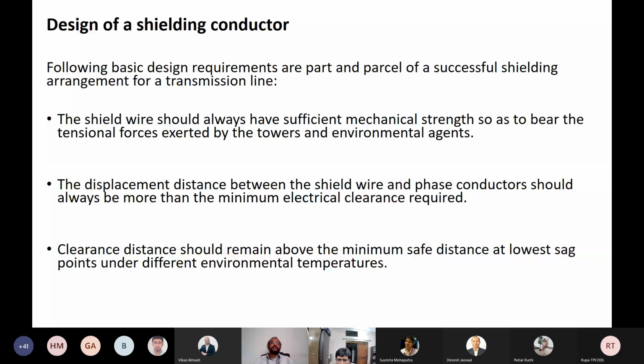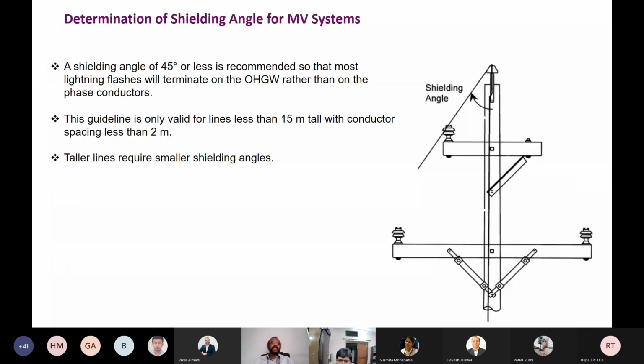Then determination of shielding angle of MV systems. Now, when it comes to distribution lines, a shielding angle of 45 degrees or less is recommended so that most lightning flashes will terminate on the overhead grounded wire rather than on the phase conductor.